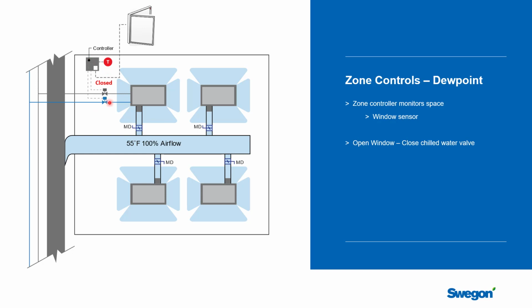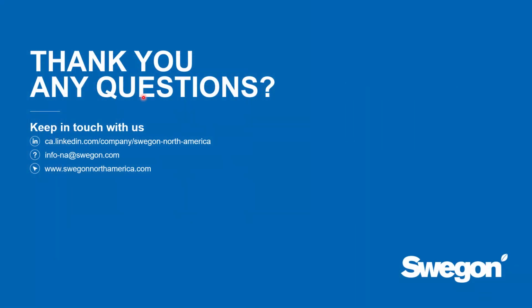And remember that if they close that window, very quickly this primary air will dry the space out as it brings in air that's been conditioned and dehumidified, and your chilled water valve will be allowed to operate, and they'll be able to get mechanical air conditioning in the space. So that's a quick rundown about common ways of managing a constant volume chilled beam system, and the most common questions that come up that can be used for doing a control system.